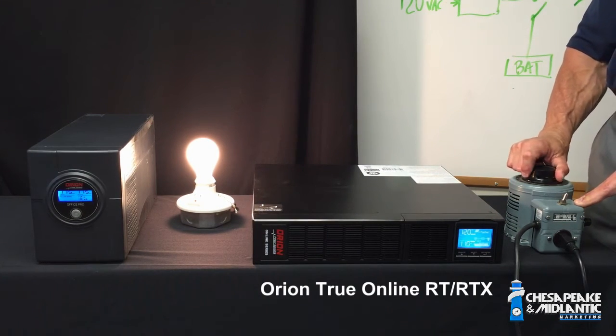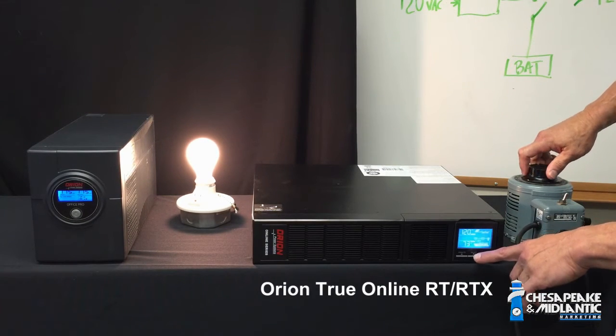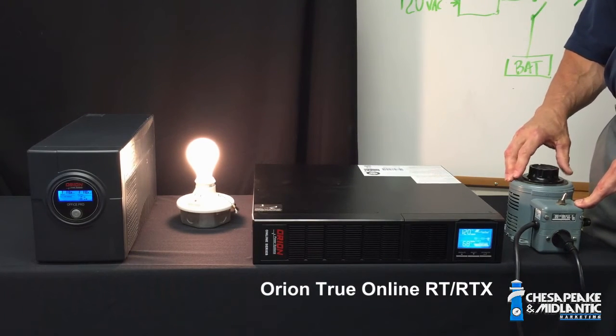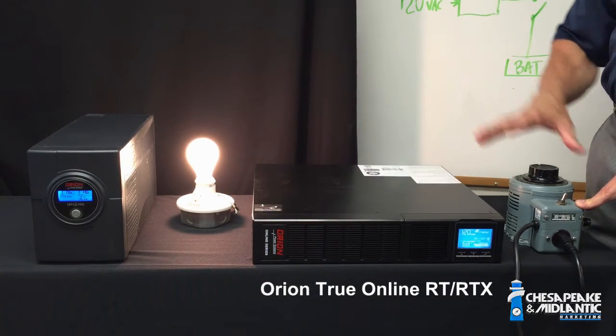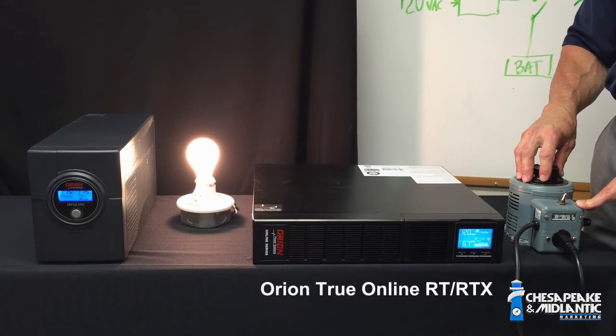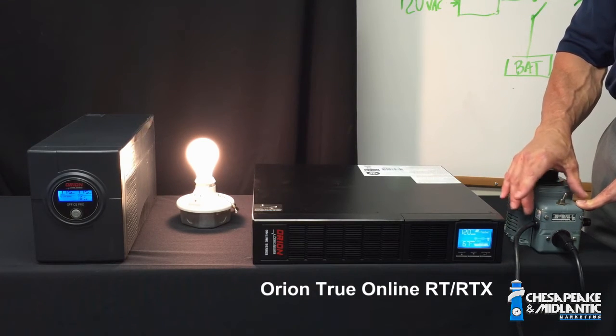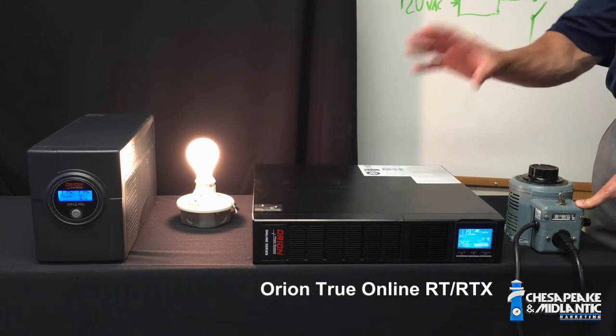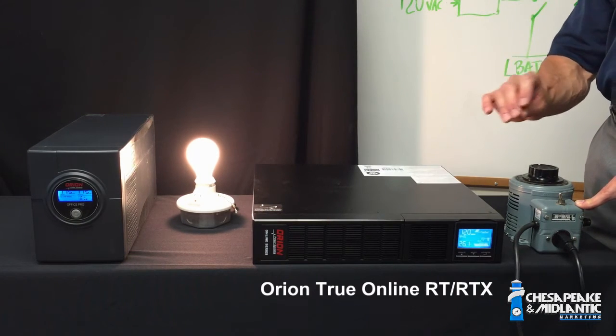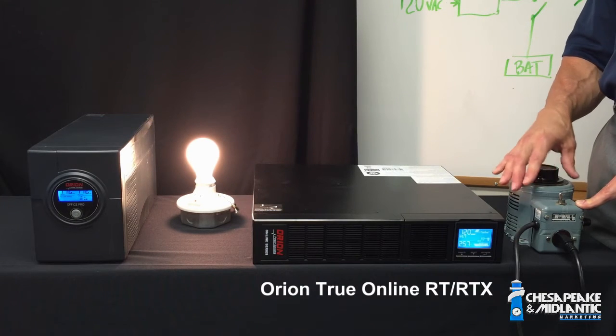As I turn the voltage regulator down, you will notice on the display that I have dropped the power down to about 60 volts AC. There's no change in my light bulb — this would be a brownout. I've reduced power but I'm still providing the 120 volts AC output. I can even go further and have a true power failure from the grid by turning this off. As you will see, continuous power to the light bulb. There is no flicker, no delay. It continues to provide power.